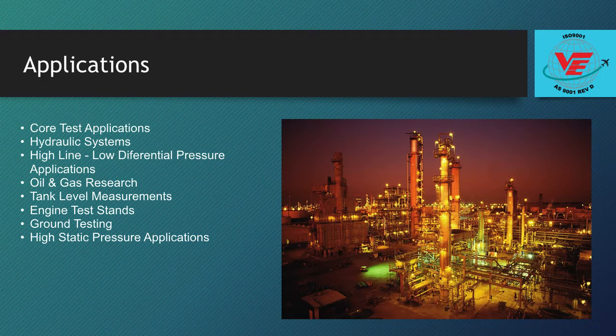The P365 pressure transducer has been used in a wide array of applications, from core test applications to hydraulic systems, high-line low differential pressure applications, oil and gas research, tank level measurements, engine test stands, ground testing, and high static pressure applications. Like all Validyne pressure sensors and pressure transducers, the P365 does not contain any silicone or oil in the sensor cavity. This makes the P365 ideal for applications in extreme temperature environments.